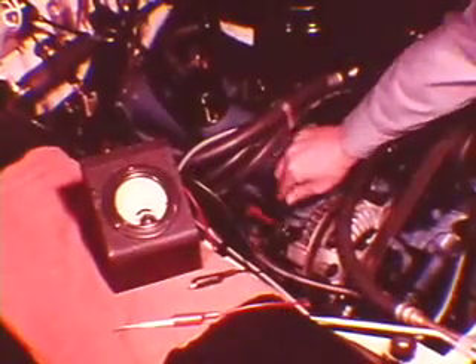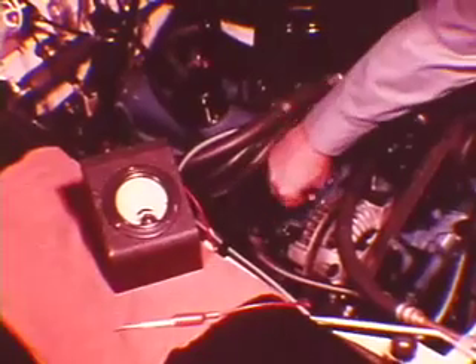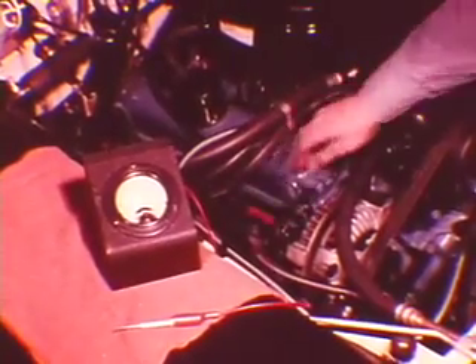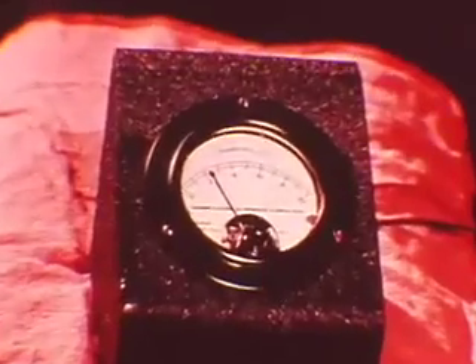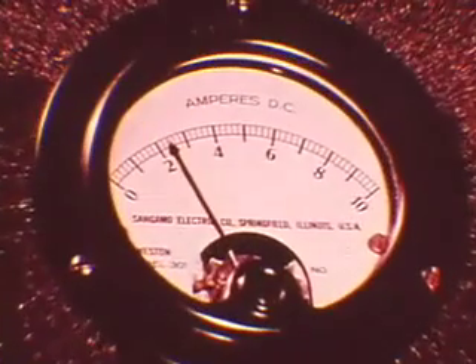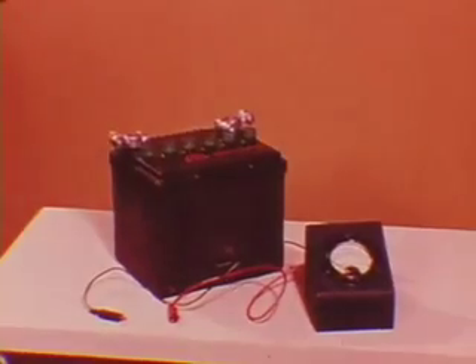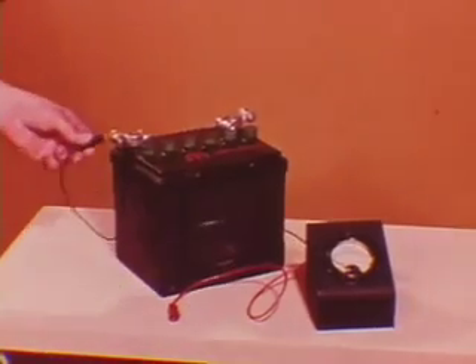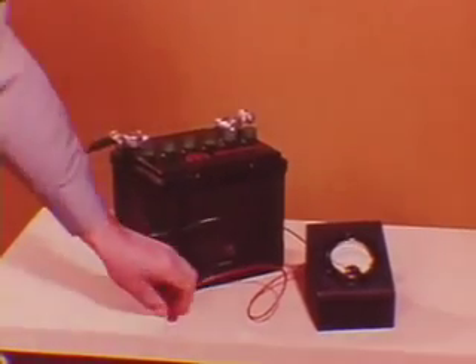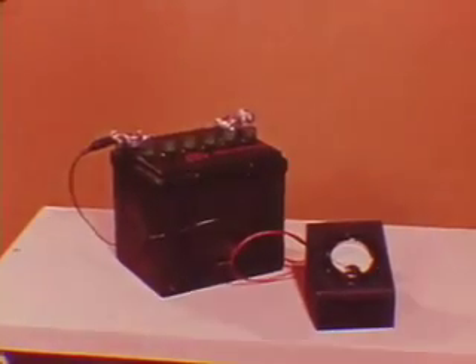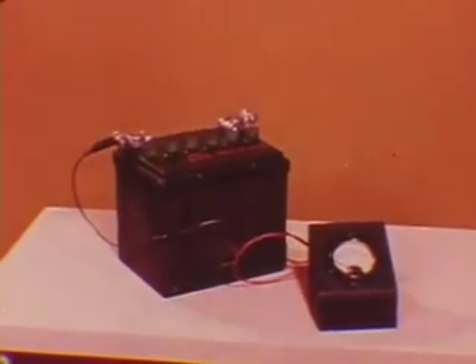An ammeter must always be connected in series, so that all of the current flowing in the circuit flows through the ammeter. That means you must disconnect at least one wire to connect an ammeter correctly. Never connect an ammeter across a circuit, the way you connect a voltmeter. If you connect an ammeter in parallel, you'll fry it for sure. That's why you must connect an ammeter in series.